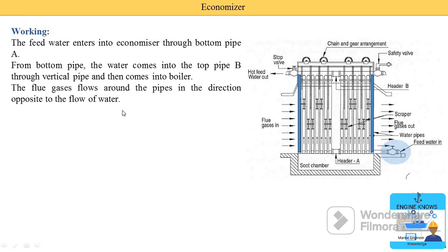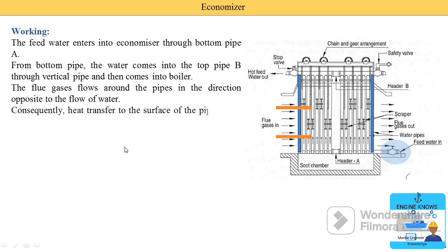The flue gases flow around the pipes in the direction opposite to the flow of water — water moves upward and the flue gases move in the horizontal direction, opposite to the water flow, as indicated by the orange arrows. Consequently, heat transfer to the surface of the pipe takes place. Water flows inside the pipe and flue gases pass outside, heating the pipe material, which in turn heats the water.